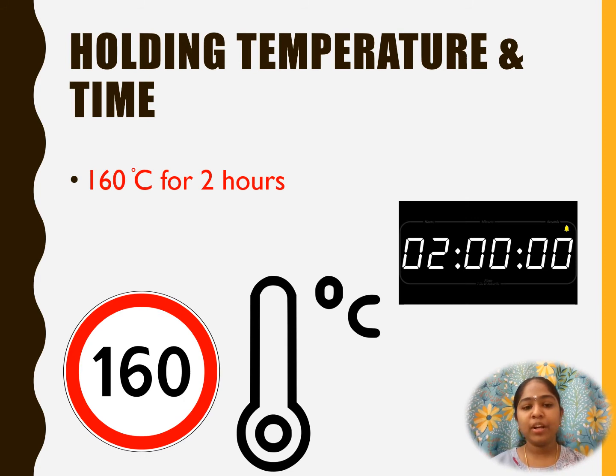Holding temperature and holding time. The time and temperature required for the complete sterilization of the material placed. Holding temperature is about 160 degrees. For holding time, 2 hours is required for the sterilization in hot air oven.